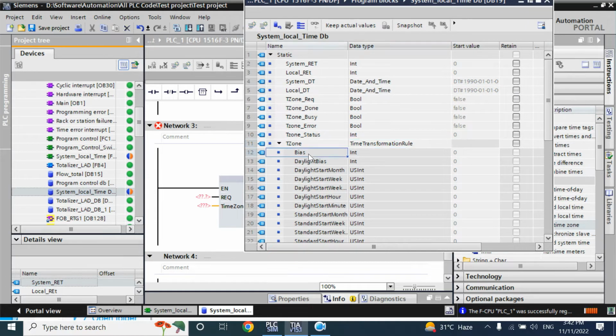It has a bias tag, that is an integer. That bias tag is the time offset, how much time will be shifted from the UTC to your local time. Suppose for my case, it is plus 6, so UTC plus 6. You have to write it not as plus 6, but in minutes.